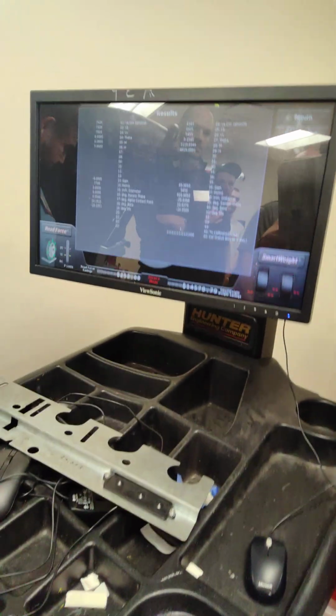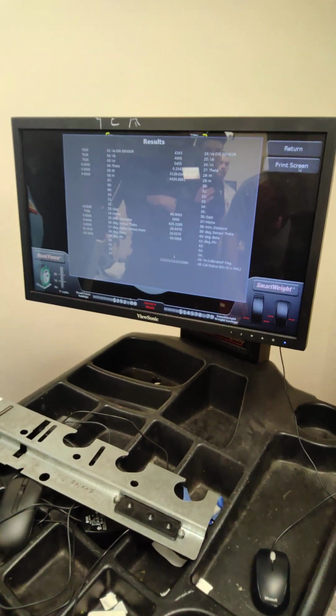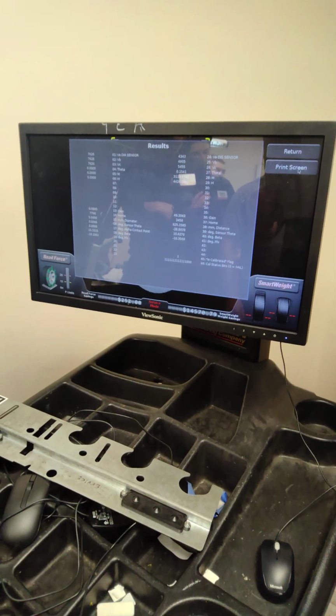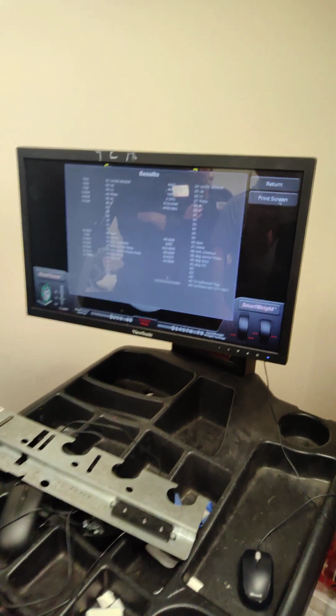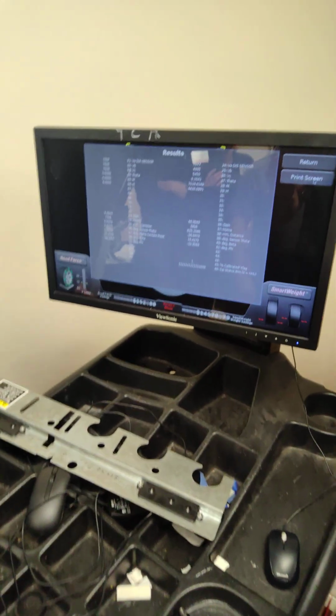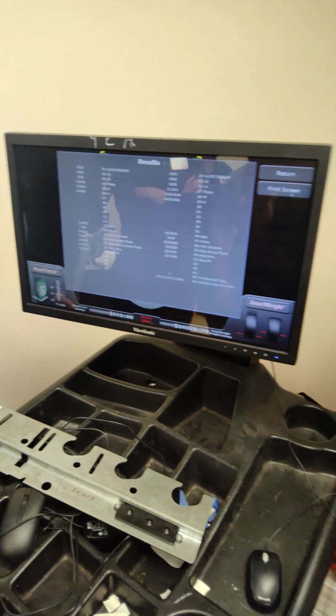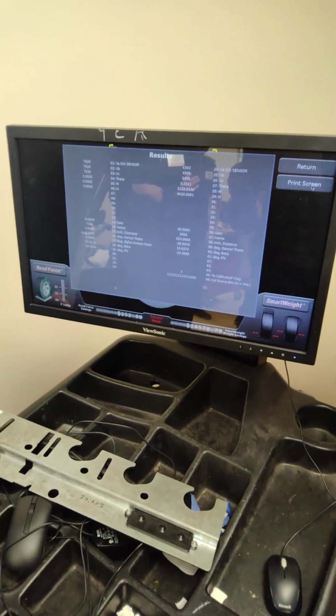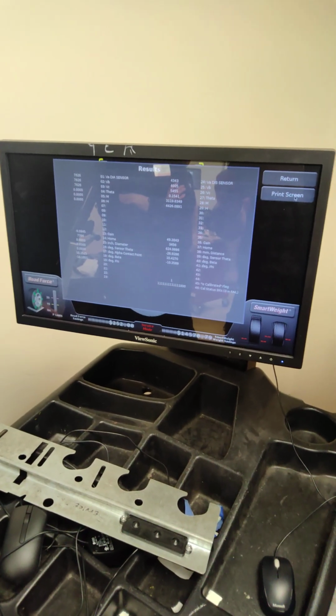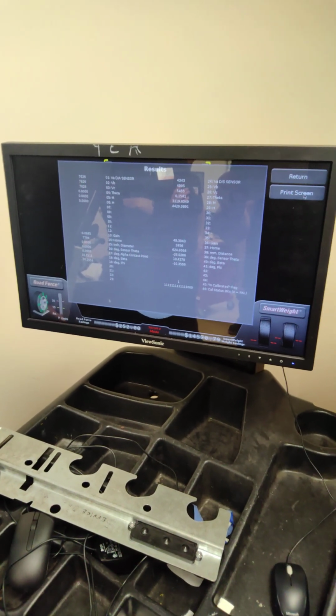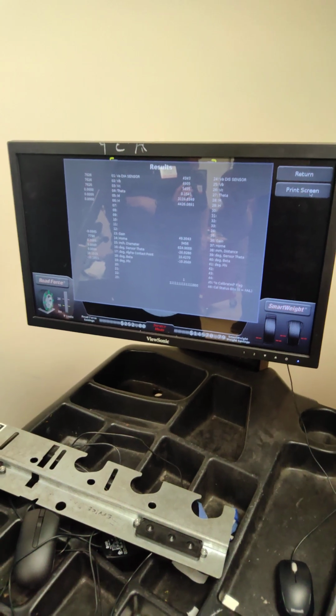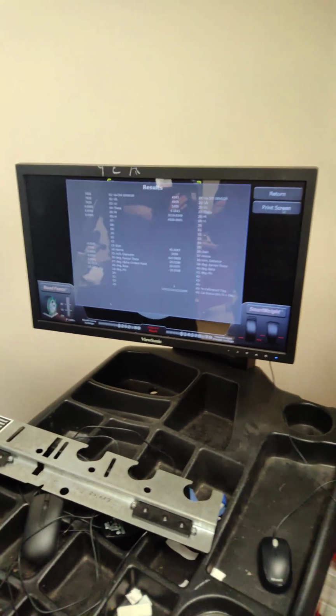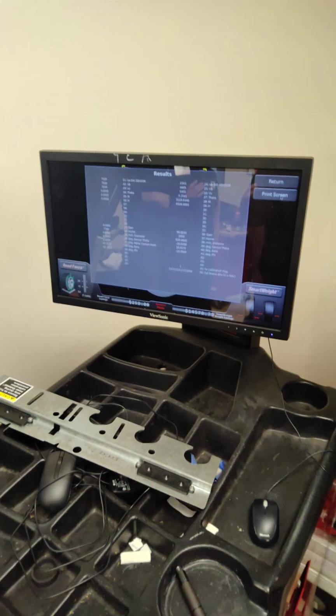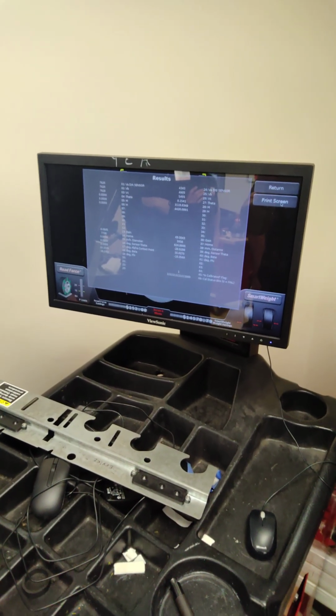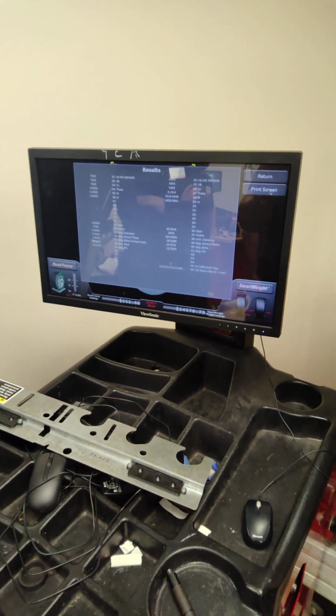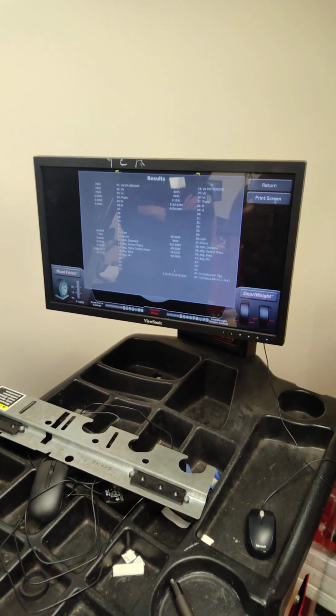When you're in regular user mode and you go to calibrate the balancer, it remembers the last calibration until the current calibration passes. Then it overwrites it. So if you're in regular user mode and you calibrate something and it fails, the balancer is not left inoperative. It just reverts back to the old calibration, but the warning message says you failed a calibration. Please contact your service advisor, service technician.